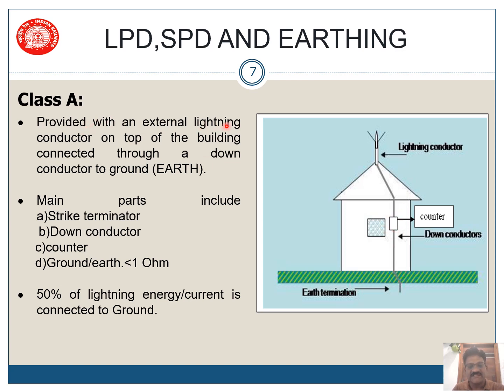So it is an external lightning conductor on top of the building, connected through a down conductor to the ground. Generally a 35 square millimetre copper conductor or a strip is used to take the lightning current to earth. The main parts include the strike terminator. So this is your strike terminator. This is your down conductor along with a counter. This counter is provided outside the building, and then the ground earth, which shall be less than 1 ohm. 50% of the lightning energy or current is conducted to ground with the help of Class A lightning protection.